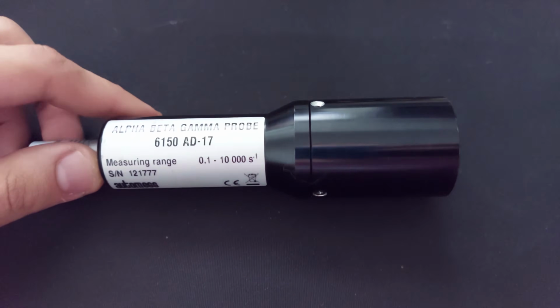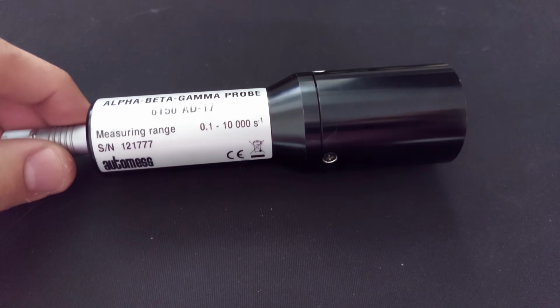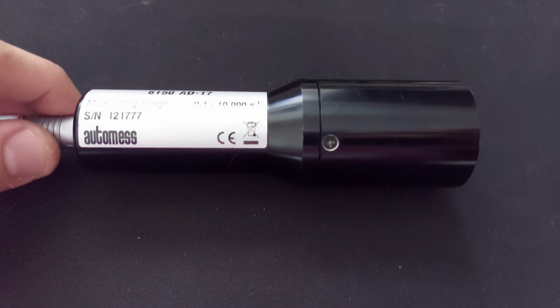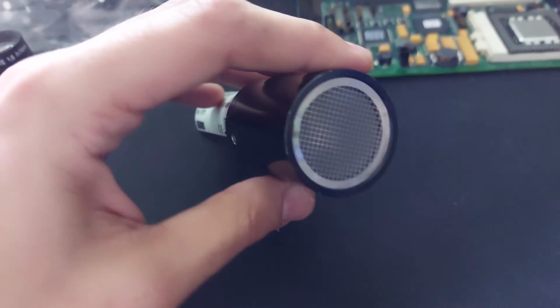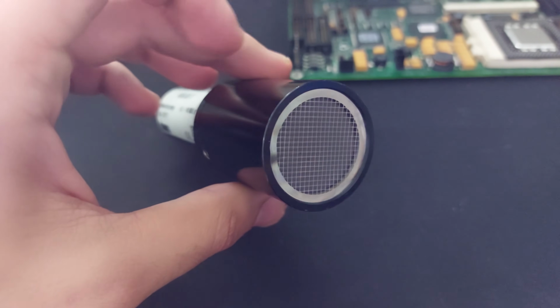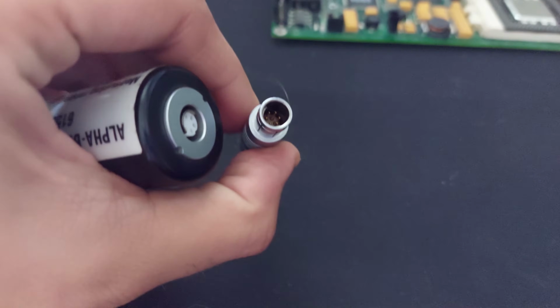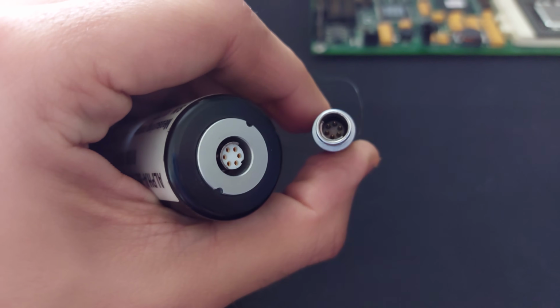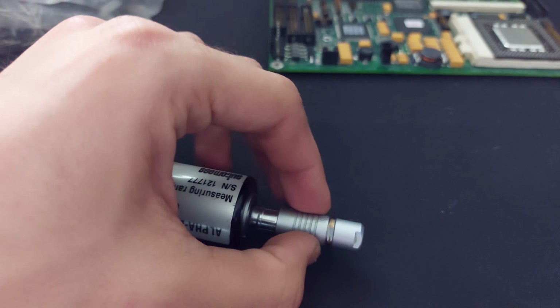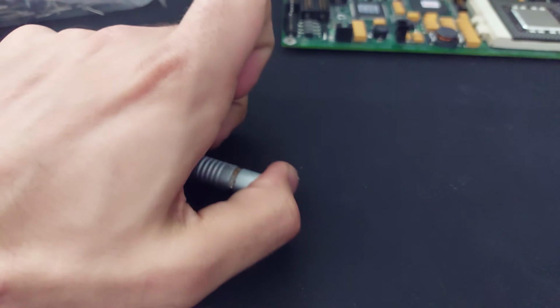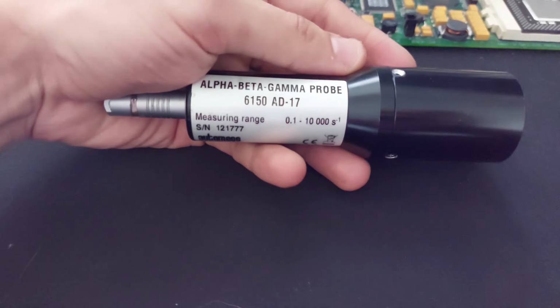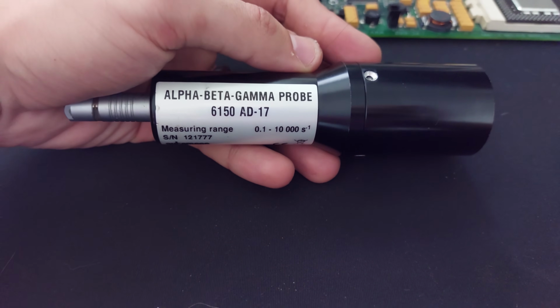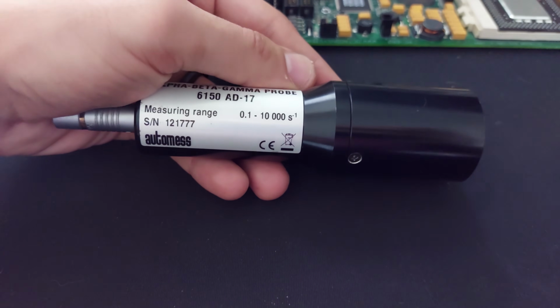First up is an Automess AD17 Alpha Beta Gamma probe. Automess is a German manufacturer of Geiger counters, dosimeters, and other radiation detection equipment. This is an end window probe, so you can see there's the mica window behind that mesh. It has this weird and very expensive Fischer connector. It's a 6-pin. These are hard to connect to a cable because they have very tight requirements in how you have to strip the wires and how you have to solder them, and assembling the plug is very difficult. I used to do a lot of these when I worked for a research institute when I was a bit younger. So let's take it apart and see what's inside.